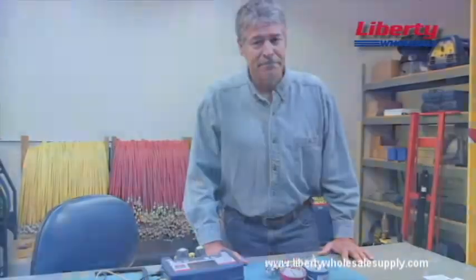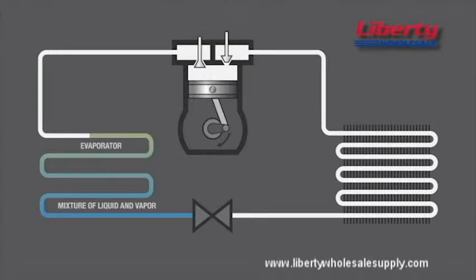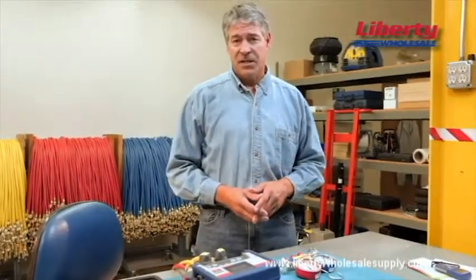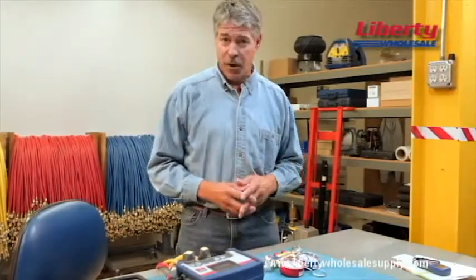First, let's look at superheat. As refrigerant enters the evaporator, it's in a liquid state. As heat is added to the liquid, it will turn to a vapor at its boiling point or saturation temperature. After the refrigerant has boiled to vapor, any temperature of the vapor above the saturation temperature is the superheat. Superheat is then any temperature of a gas above the boiling point for that liquid. The superheat calculation lets you know if the amount of refrigerant flowing into the evaporator is appropriate for the load.